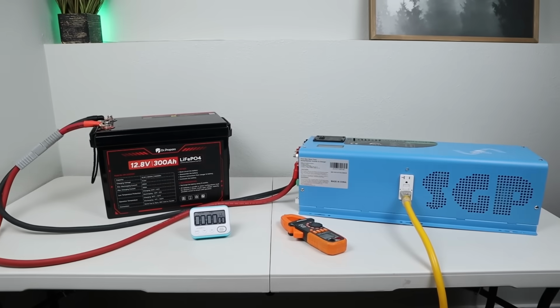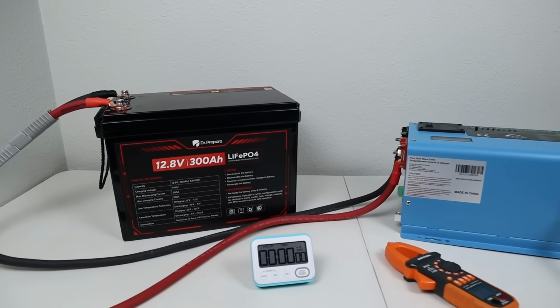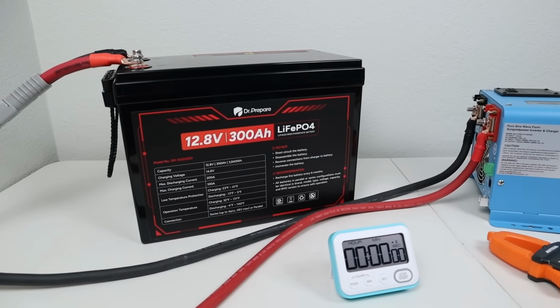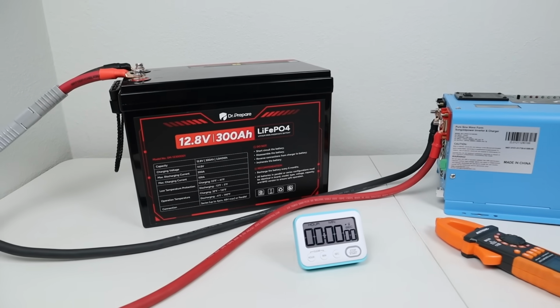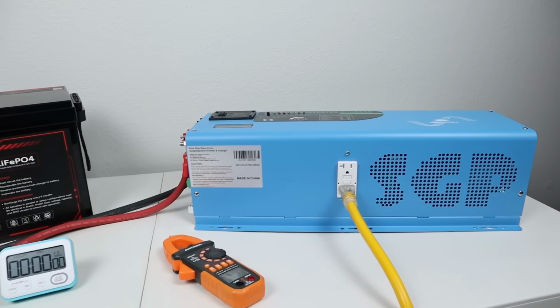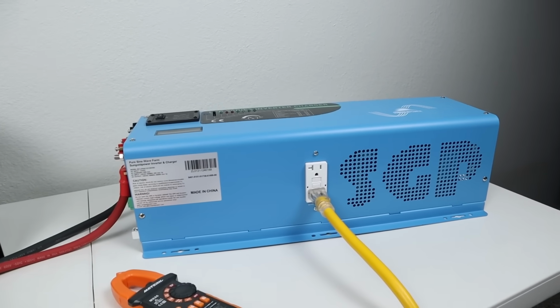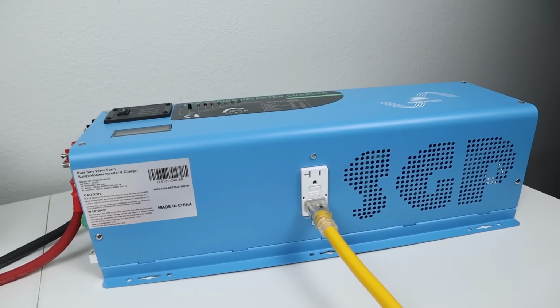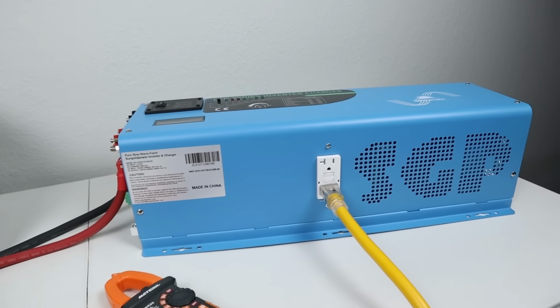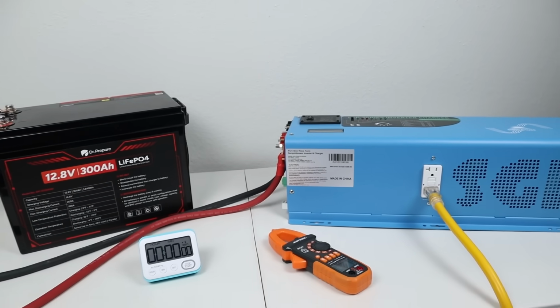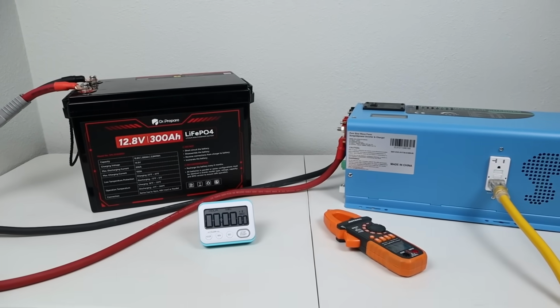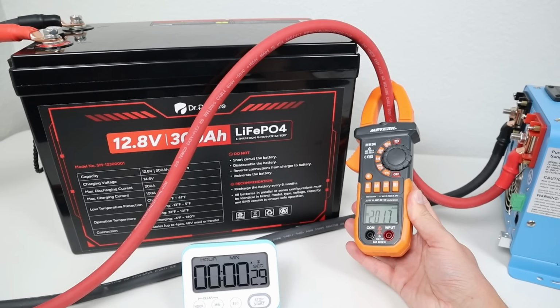Now moving on to the next test, I want to see if the battery can handle the maximum discharge current of 200 amps for 15 minutes. Now to test that out, I will be powering up a 2600 watt load on this SunGold Power low frequency inverter. Now this inverter is rated for 4000 watts, so it should handle it with ease. So let's go ahead and get it started, and we'll start the timer. Now it's taking me about a minute to zero in the load here. You can see on my clamp meter we're showing 201.8 amps. I've started the timer, so let's see if it can handle it for 15 minutes.